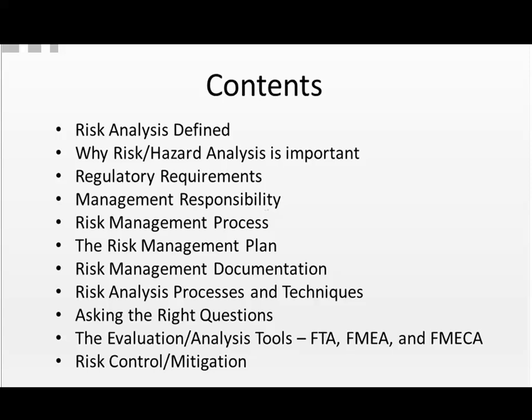Risk analysis plays a key role in the development of a medical device. Risk analysis is a structured tool for the evaluation of potential problems which could be encountered in connection with the use of taking a drug or using a medical device or instrument. Manufacturers are expected to identify possible hazards associated with their medical device design under both normal and fault conditions. During the process, if any risk is judged unacceptable, that risk must be reduced to acceptable levels by appropriate means.